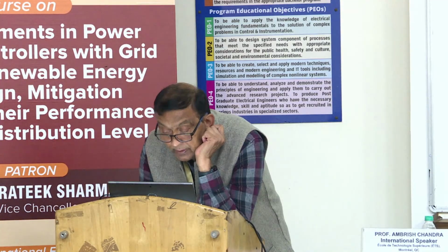If you see this, voltage per unit against time, this is the limit. The minimum voltage limit is this. I will tell you how much it is. The maximum voltage limit is this. And mandatory right through: within this range of voltage at the grid, DER should remain connected. While here in this region, if they want, they may trip.